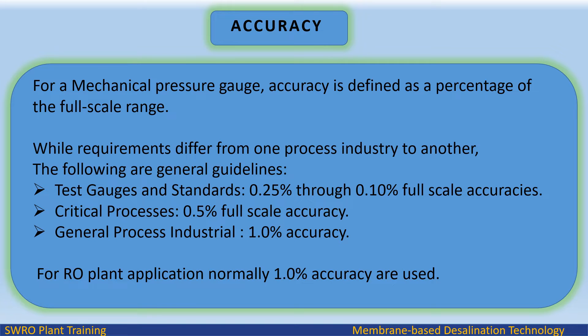Accuracy: For a mechanical pressure gauge, accuracy is defined as a percentage of the full scale range. General guidelines are: test gauges and standards — 0.25% to 0.1% full scale accuracy; critical processes — 0.5% full scale accuracy; general process industrial — 1% accuracy. For RO plant applications, normally 1% accuracy is used.